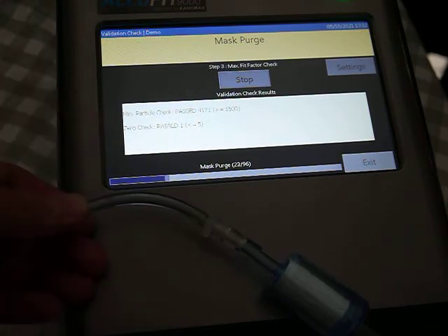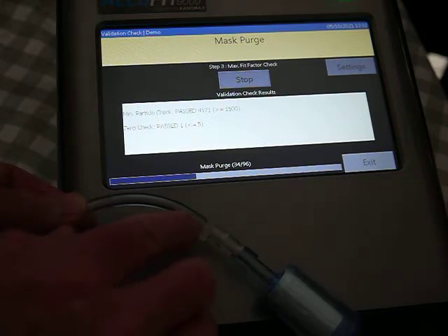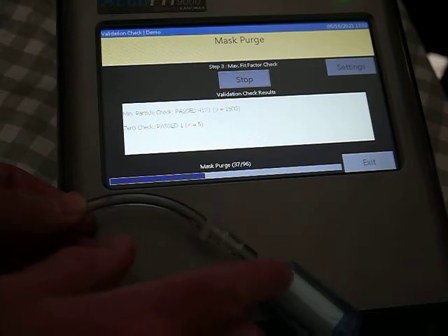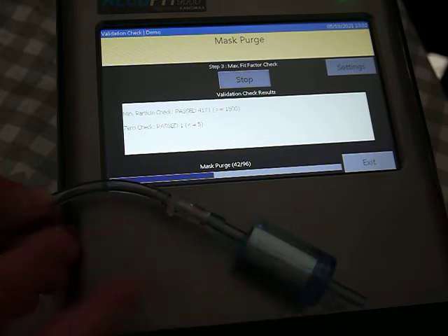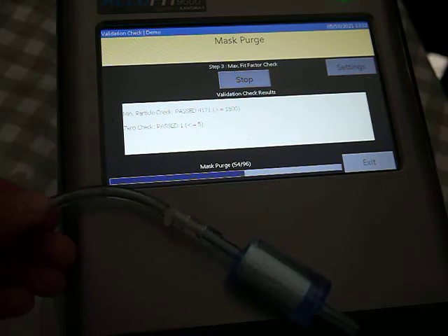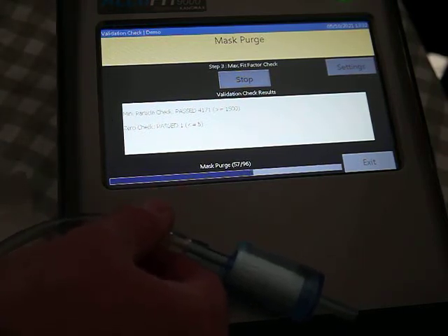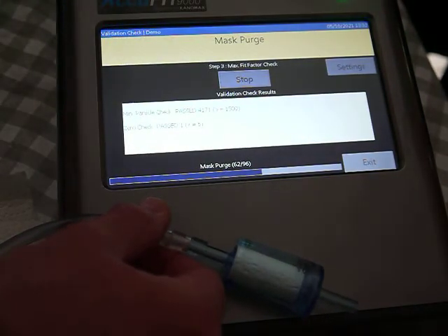We're just waiting for it to complete its verification. Sometimes you can get little cracks in the tubing here, or if this HEPA filter gets dropped very much, you can have cracks in the housing. So if this doesn't pass the 0 check, there can be reasons like that why it may not be passing. If you don't get enough particles in the air, if your alcohol in your chamber is old, it may have soaked up too much moisture, and that can also cause a low particle count.